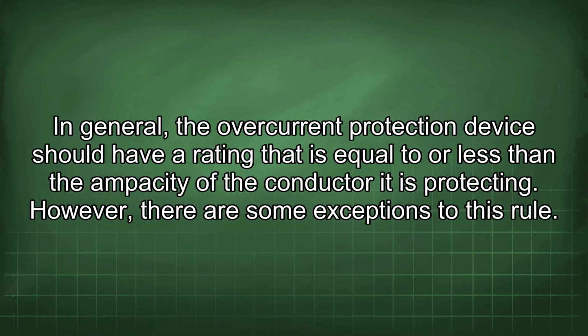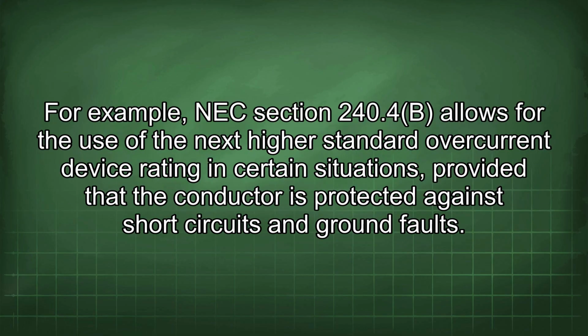In general, the overcurrent protection device should have a rating that is equal to or less than the ampacity of the conductor it is protecting. However, there are some exceptions to this rule. For example, NEC Section 240.4(B) allows for the use of the next highest standard overcurrent device rating in certain situations, provided that the conductor is protected against short circuits and ground faults.